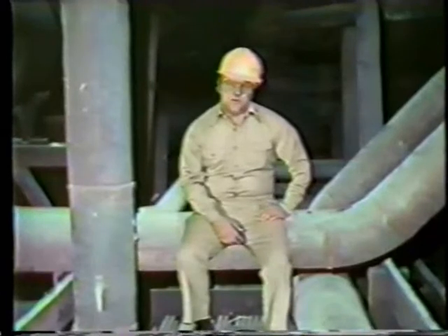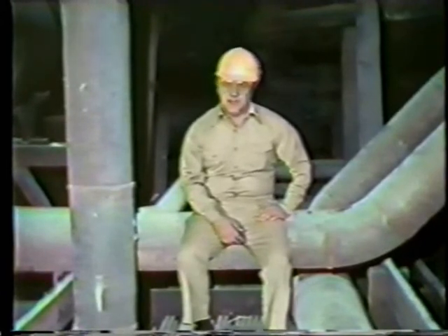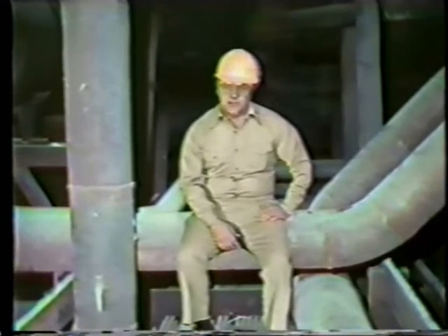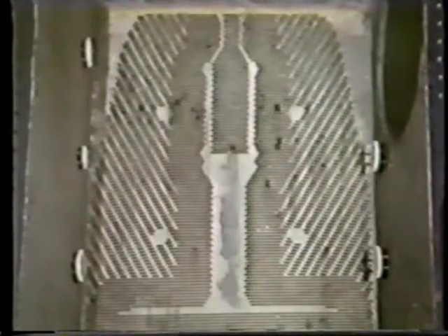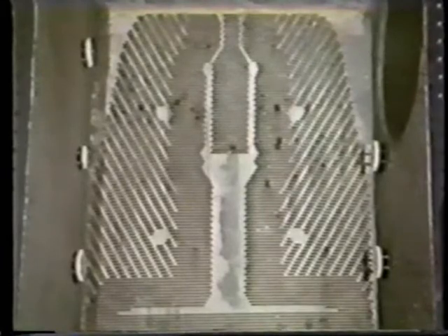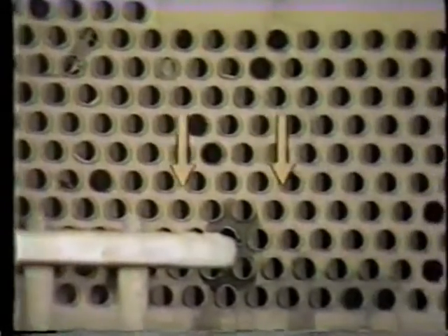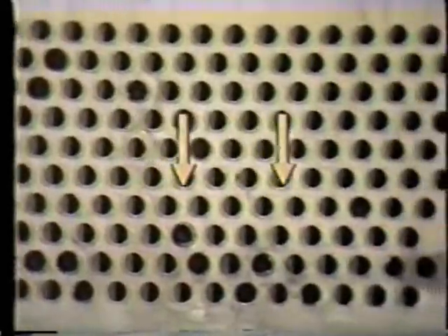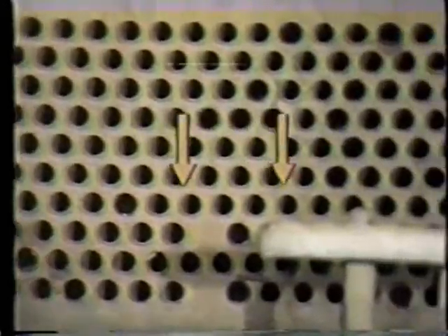It's difficult to see the flow path of steam down the steam inlet lanes from inside. Let's look at the flow path from an end view of the condenser. Even though we're looking at the tube sheet, this view will help us show the flow path of steam through the steam inlet lanes. As the steam flows through these inlet lanes and around the tubes, latent heat is removed from the steam. As we discussed earlier, the steam condenses and drips off the tubes into the deaeration trays and eventually falls into the hot well.